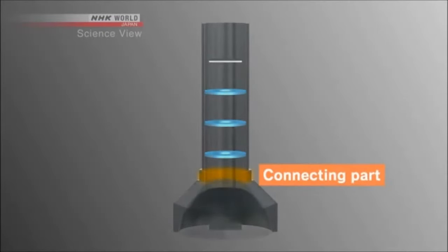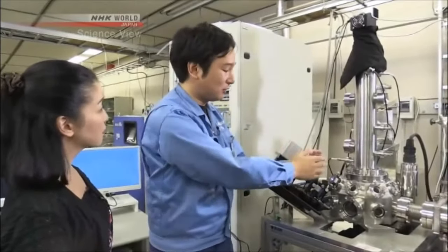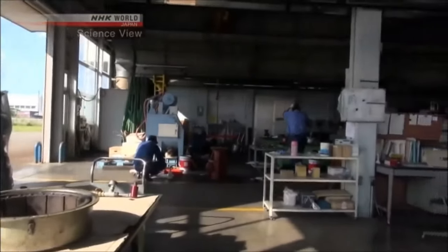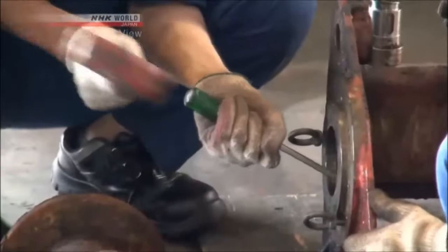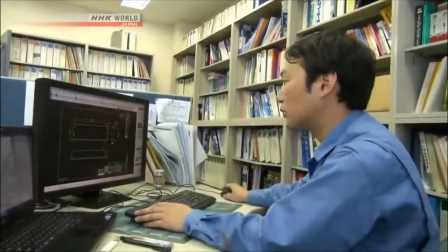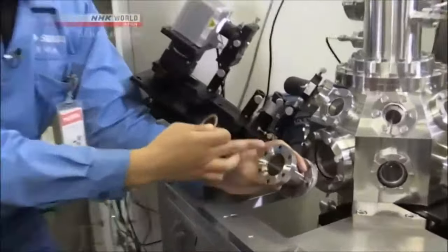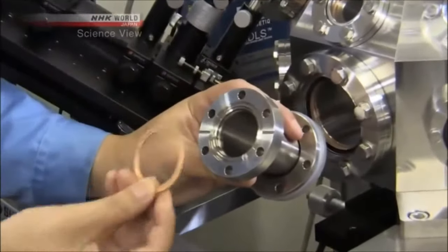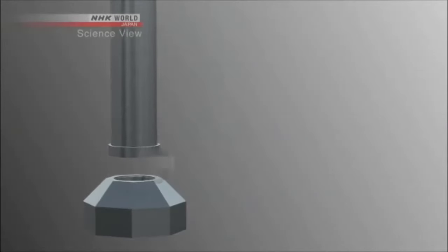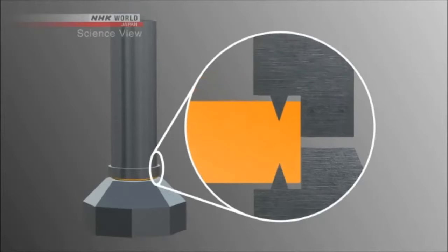The area where the sample is placed and the connecting part of the pipe were key to achieving both requirements. If it was entirely welded, the heat from welding would cause it to deform and the accuracy would be off. The Takumi's company was involved in large industrial products such as parts for fishing trawlers, but making microscopes required incomparably higher accuracy. The Takumi then looked for a method to improve that accuracy. The joint part is machined sharply, called a knife edge, and a part called a gasket is attached there. Looking at the cross-section, you can see claw-like sharp edges. A metal gasket is placed in between and locked with a claw.